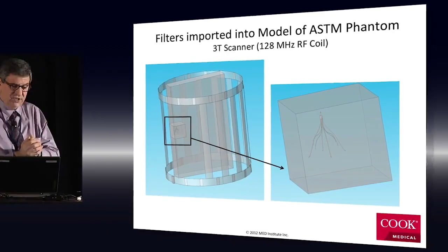But in any case, they're in long enough where it's a possibility that you'll be scanned and they may heat up, and it's the same question. Can you keep the temperature rise under 6 degrees and feel good about the safety of the device? So we take this CAD geometry from ProEngineer in this case, which was 7-year-old CAD data, and I'm not going to go into the issues I had of trying to get that to a modern format. Okay, but very intricate. These wires are less than a millimeter in diameter. I pulled in the full resolution of the data, pulled it into COMSOL, struggled for many weeks trying to resolve domains and so forth with such crummy geometry information, slightly corrupted slivers and so forth, and getting it to resolve the tolerances.